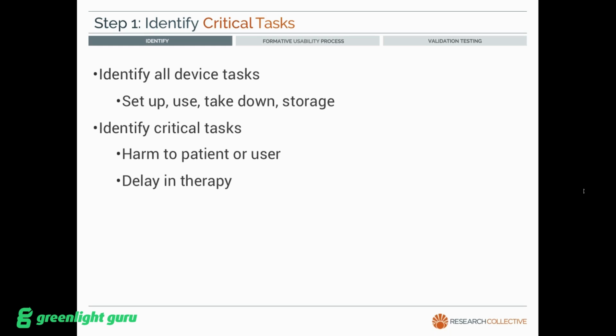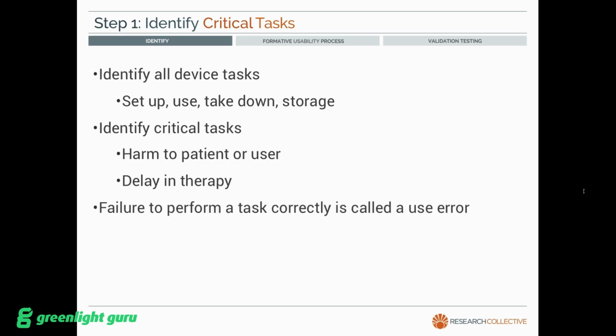Critical tasks are defined as those that, if not performed correctly, would lead to harm to the patient or user. That's simple enough, but it's important to note that harm can also mean a delay or lack of therapy. Failure to perform one of these critical tasks is what we call a use error. And notice that it's not called a user error. One of the commandments of human factors is: blame not thy user. You will never see a human factors report calling something a user error, because we don't attribute the blame to the user. We attribute it to the device itself, and we think of ways that the interface can be designed to minimize task failures through good design.